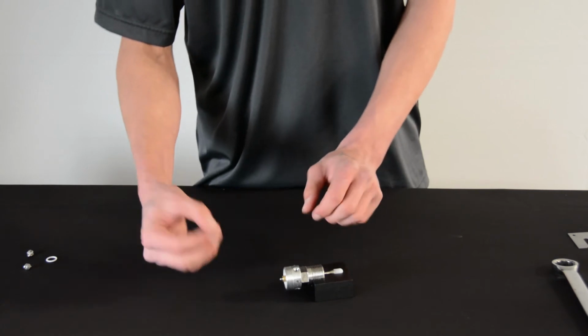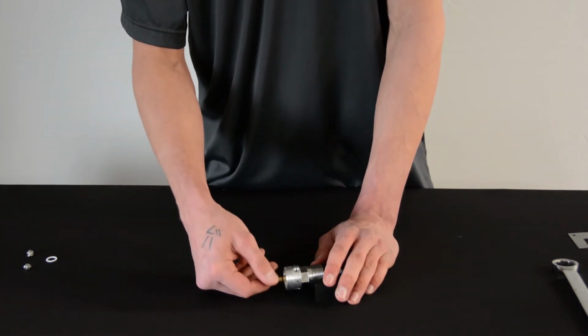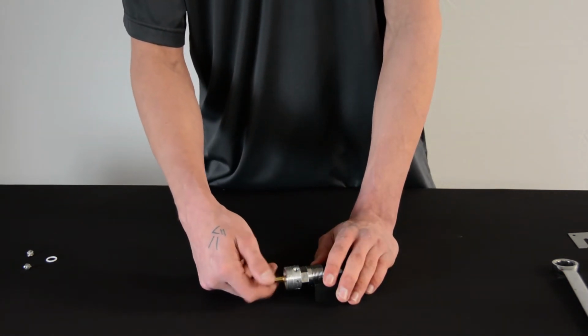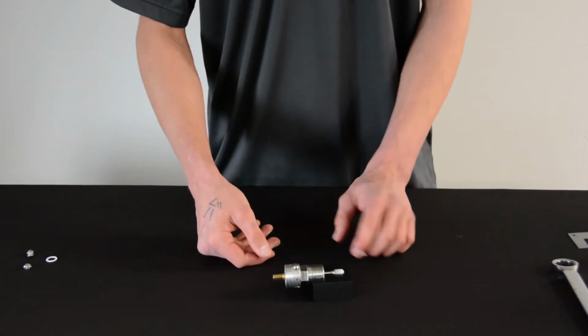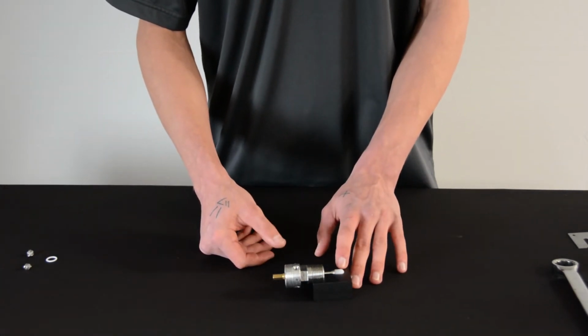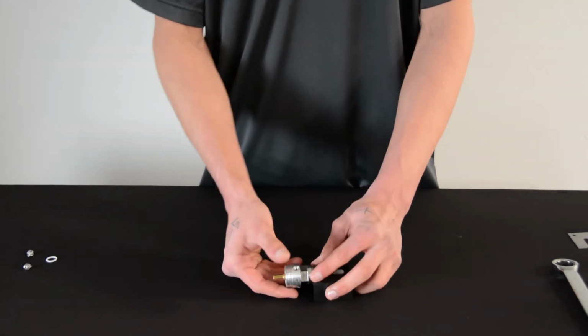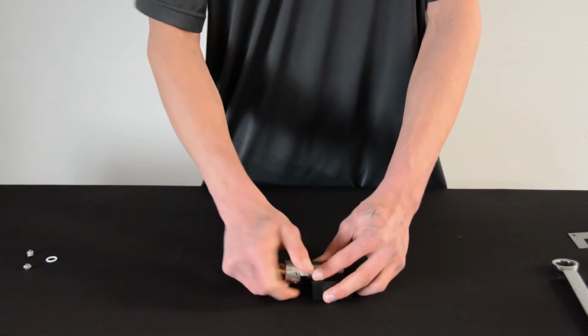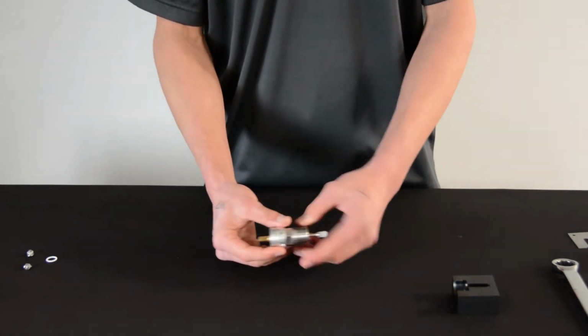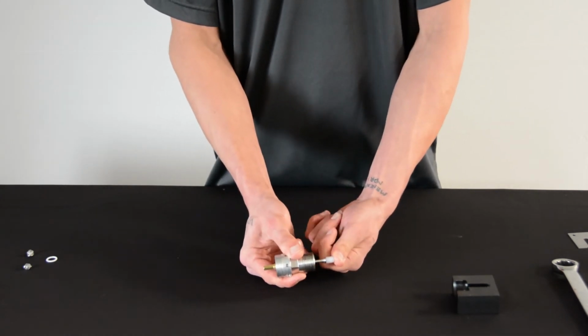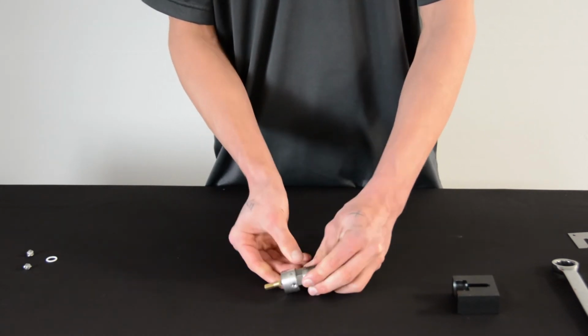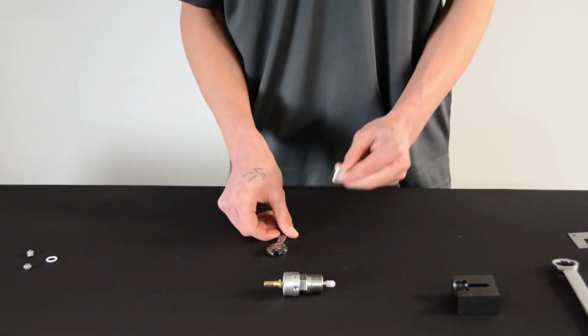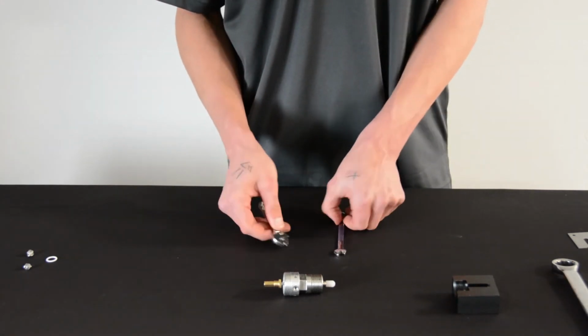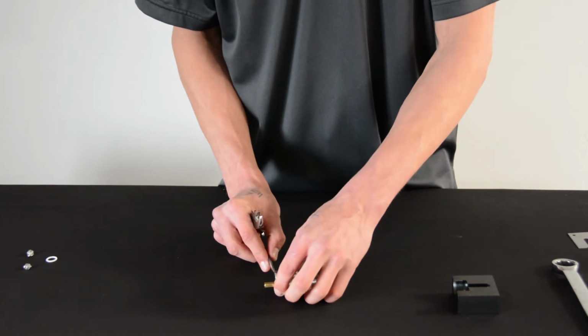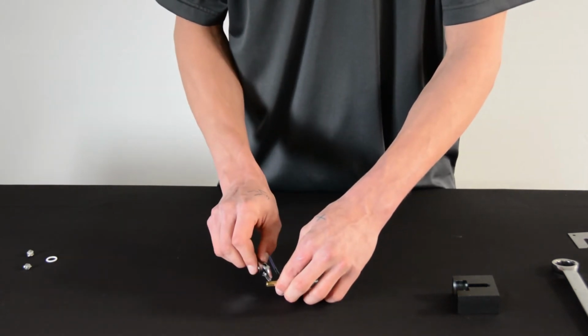Then take your locking nut indicator and thread onto the bottom of the piston shaft. It is important that you don't over tighten this as well, as this will pull the plunger end off the bottom of the calibration block. You can then pull your Poppet valve out of the calibration block, push your shaft back through the Poppet valve. Using your 5/16 wrench and 1/4 inch or small adjustable wrench, tighten the piston retaining nut and locking nut indicator together.